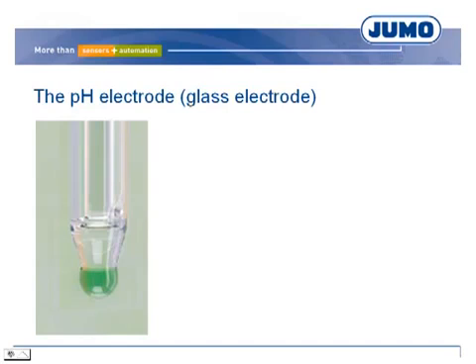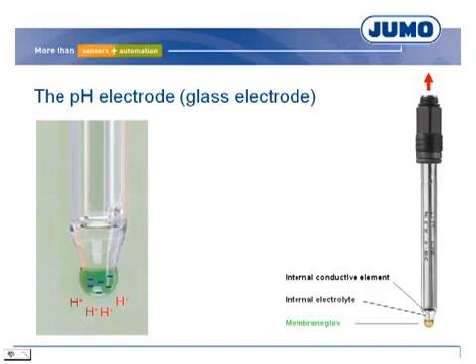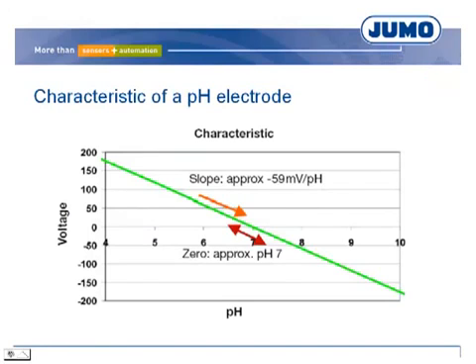The membrane glass of the pH electrode is negatively charged. The hydrogen ions carry a positive charge. The higher the hydrogen ion concentration, the more ions are gathered by the membrane glass — the more ions, the higher the potential on the membrane glass. This potential is conducted to the head of the electrode via the internal electrolyte and the internal conductive system.